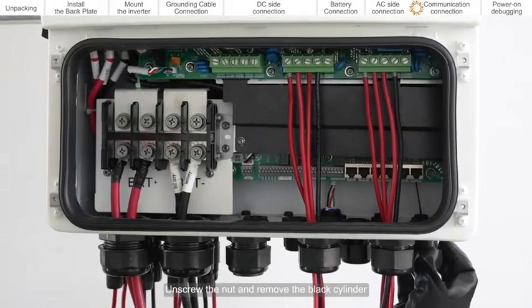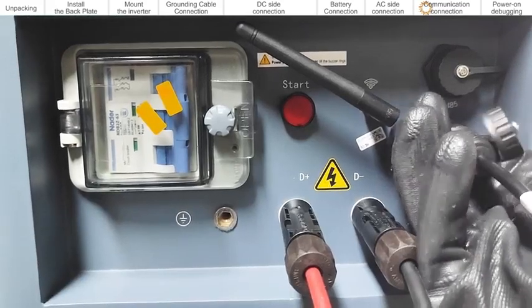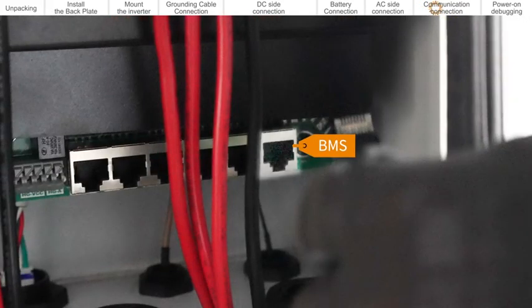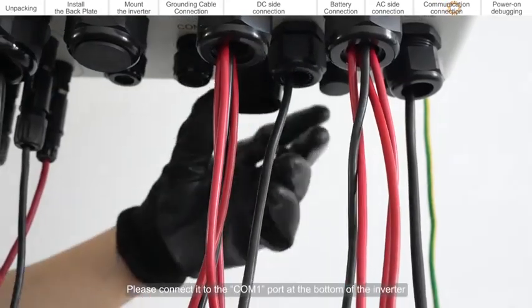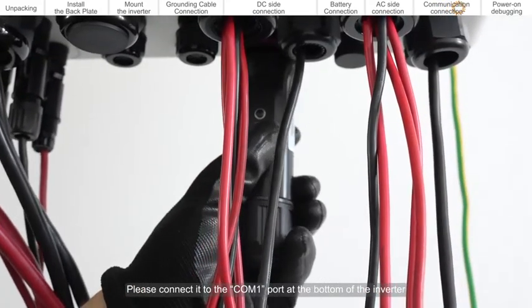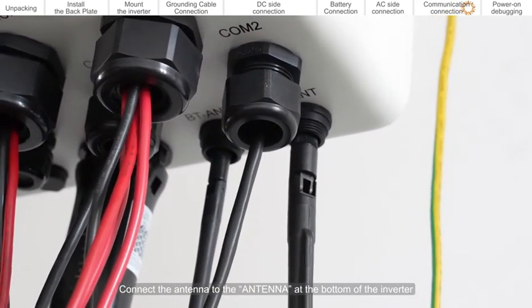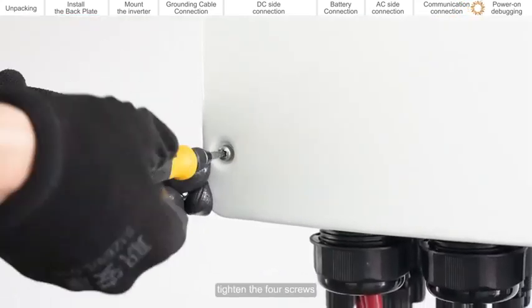Communication connection. Unscrew the nut and remove the black cylinder. Connect one end of the BMS cable to the CAN port of the battery, then connect it to the BMS port at the bottom of the inverter. Connect the CT cable to the CT port. If you choose a Solis data logger, please connect it to the COM1 port at the bottom of the inverter. Connect the antenna to the antenna port at the bottom of the inverter. Close the communication cable protection cover, tighten the four screws, and tighten the nuts.